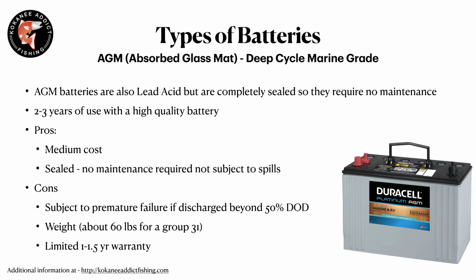Some of the cons on this battery: just like the lead acid, they are subject to premature failure if you're frequently discharging them below 50% charge. The weight on these is about 60 pounds for the same big battery, and you're going to get anywhere from a 1 to 1.5 year warranty typically.